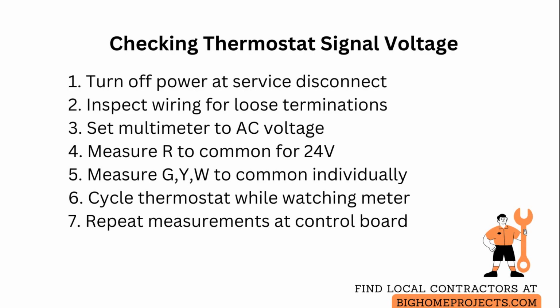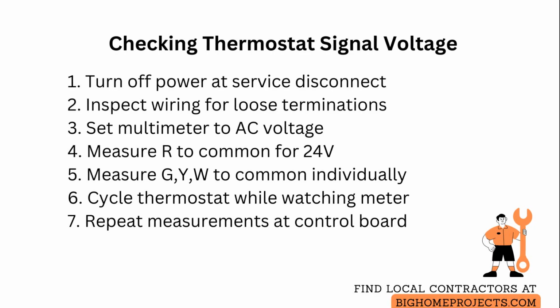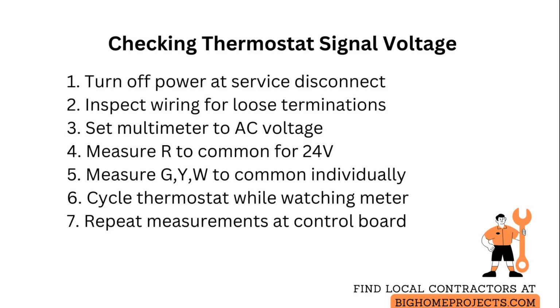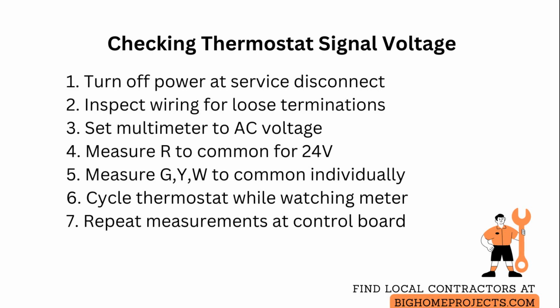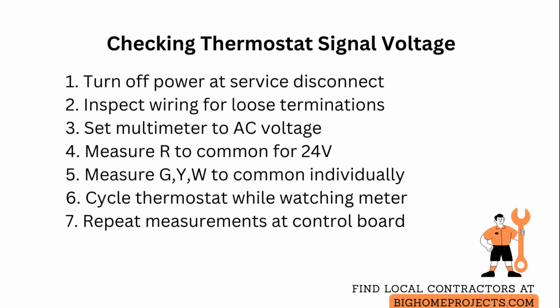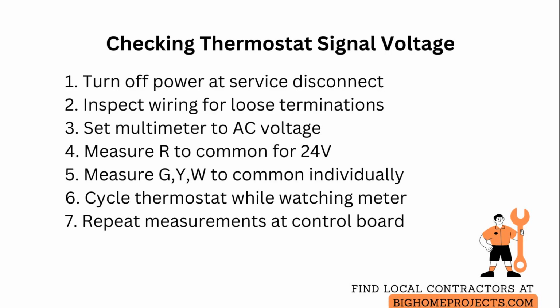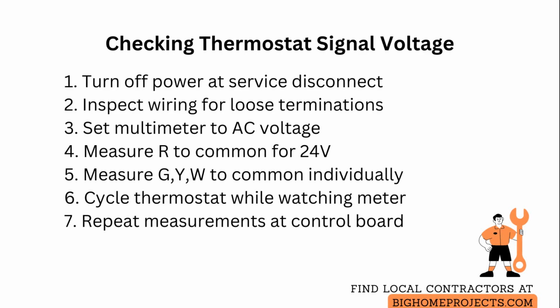Restore power, set your multimeter to AC voltage, and measure between the R terminal and common to confirm constant 24 volts. This is your reference and should always read 24 volts. Next, measure from each control signal terminal to common individually. So measure G to common, Y to common, and W to common. Expected readings are either 0 volts when inactive or 24 volts when the thermostat calls for that function.